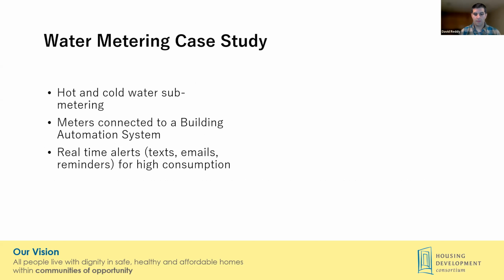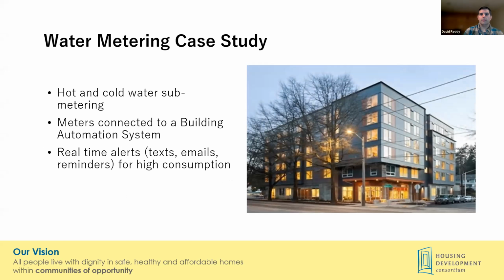So we're going to talk briefly about a case study, coming back to one of our buildings that we've learned a lot from, the Estelle. It is permanent supportive housing, so there are some caveats to the conclusions we're going to talk about here. But I can tell you that the gallons of hot water per person, a metric that is oftentimes used, should be known about for designing your system or knowing how much you're going to spend on utility bills. That number is roughly...